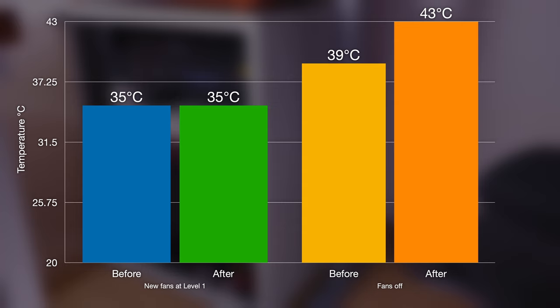So what you're seeing here is both before and after, with the fans on and off. When I've got the new fans, which are speed controlled, they're set to level 1, which is the lowest level. So you can see at level 1 on the new fans, the rack was the exact same temperature as the old fans. But of course the old fan was running at its maximum speed, so the new fans matching that at their lowest speed is pretty good.